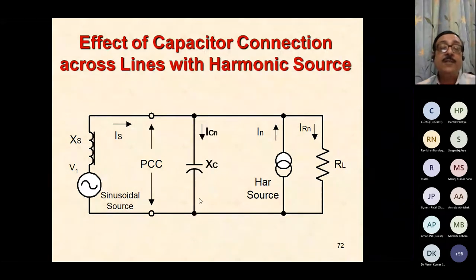I can have multiple thoughts. A capacitor connection here will permit part of the harmonics to flow through it, so it will not flow back into the supply. The supply impedance is going to be n times Xs, and this will be Xc divided by n. My understanding is that by putting a capacitor here, all the harmonics will flow here and not necessarily flow back to the source. So the source line will become free of harmonics. This is one concept by which I am putting the capacitor. The second concept might be that I want to improve power factor. Let us see what happens.